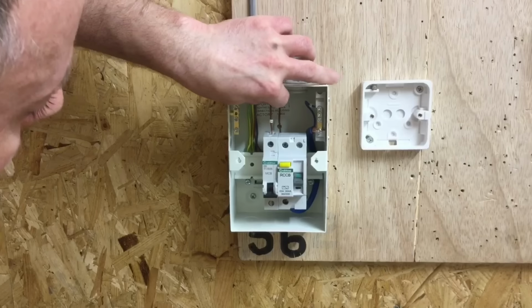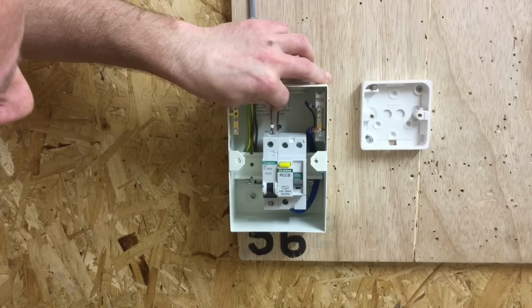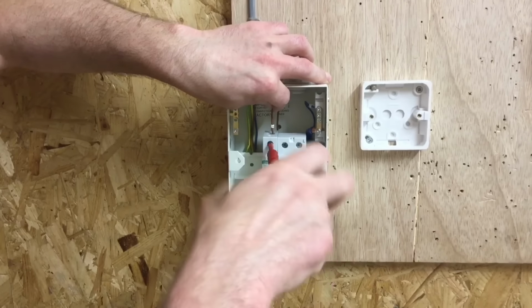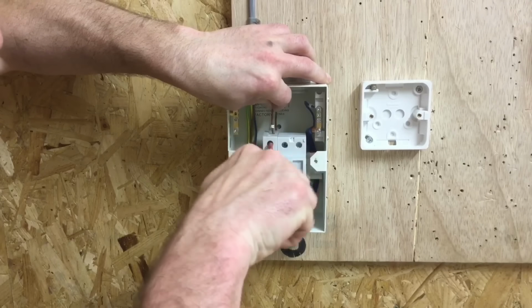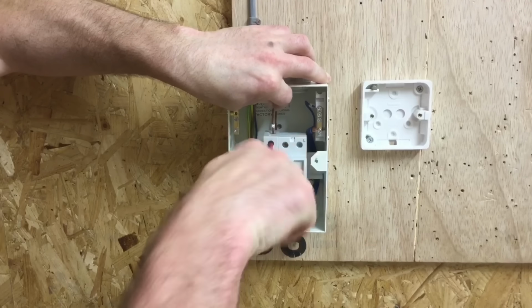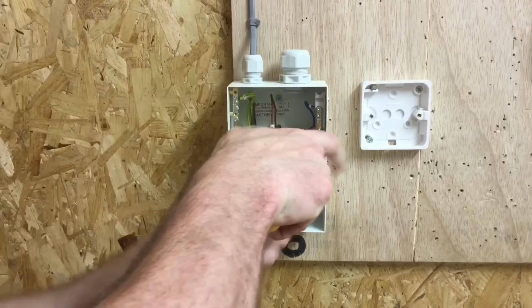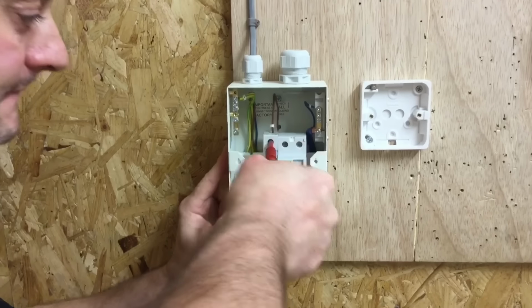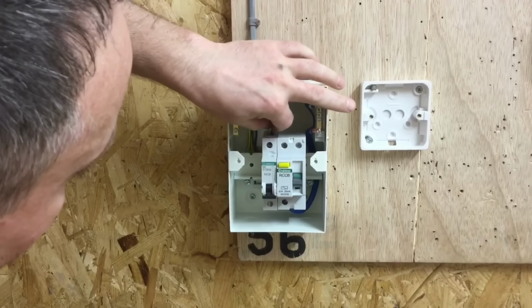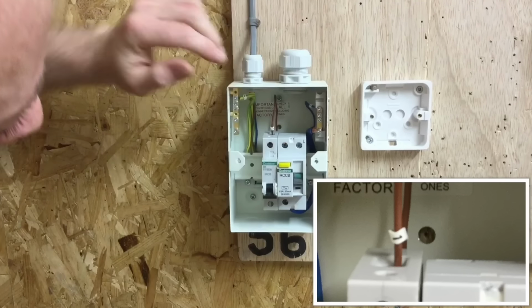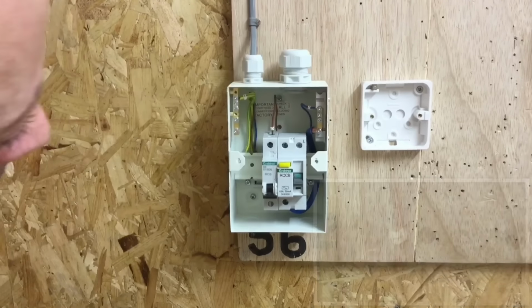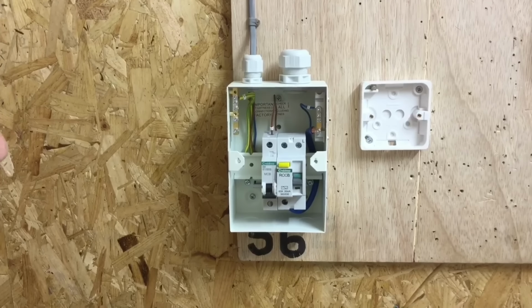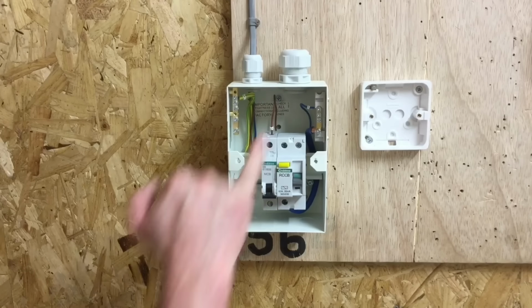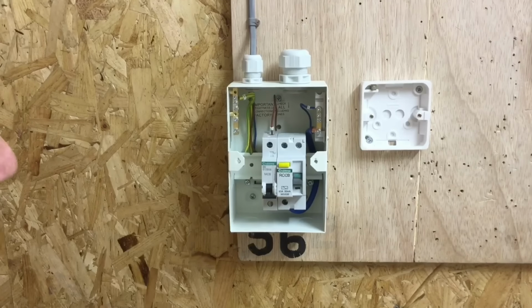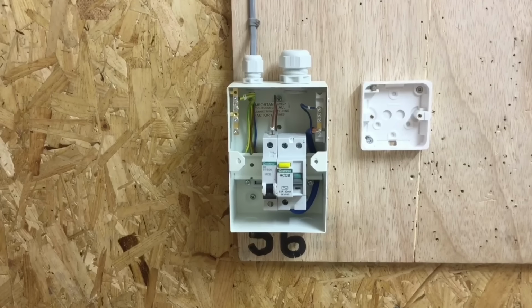So I'm ready to drop my line connection into the top of the 6 amp circuit breaker, going in with the torque screwdriver, making sure I screw into the copper, and we get it to the required torque setting. Okay, we're up to the required torque setting. I can see the number one. I need to just play around now to make sure that these come down straight and up and over straight and look super neat. But for all intents and purposes, I've made the final connections in my distribution board, labelling my neutral number one, my line number one, and my circuit protective conductor number one.